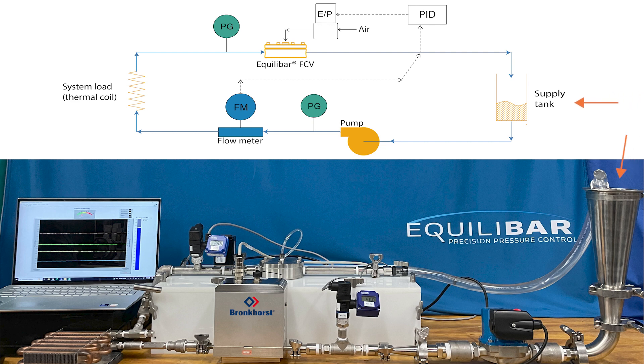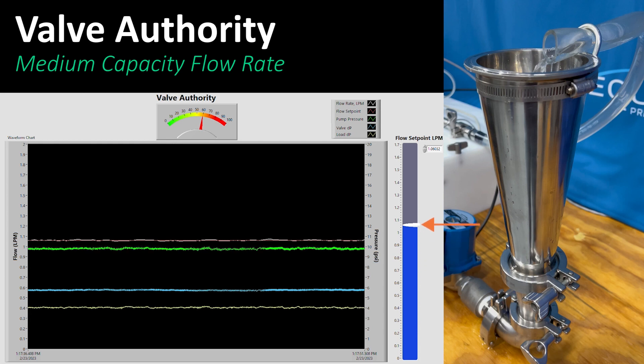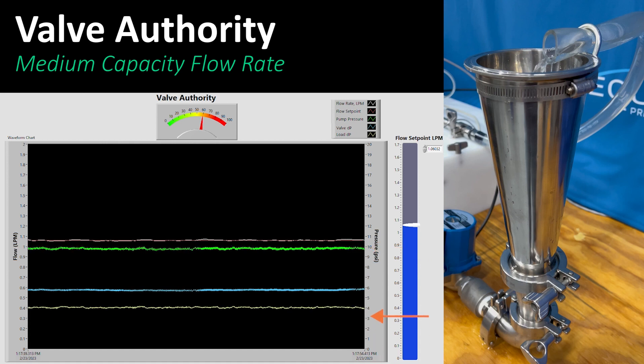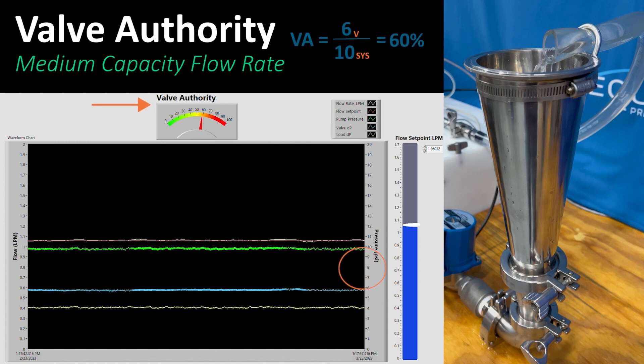Let's turn the system on and see what happens. Now we're operating the circuit at medium capacity. The flow rate is 1.05 liters per minute, or two-thirds max flow. The pump is producing 10 psi, and the coil system load has 4 psi resistance. The differential pressure on the control valve is 6 psi, so the valve authority is 6 divided by 10, or 60%. Let's explore the low flow capability.